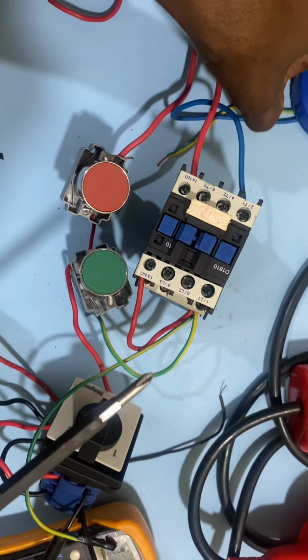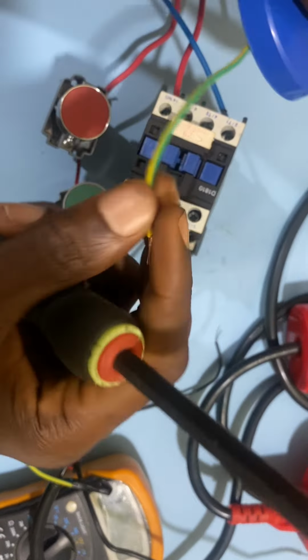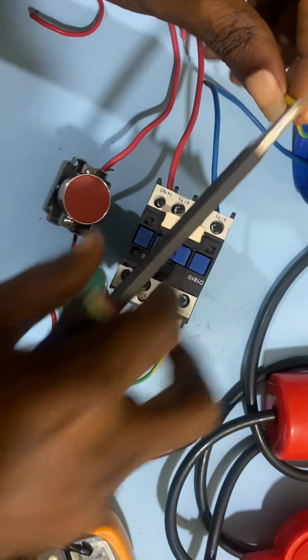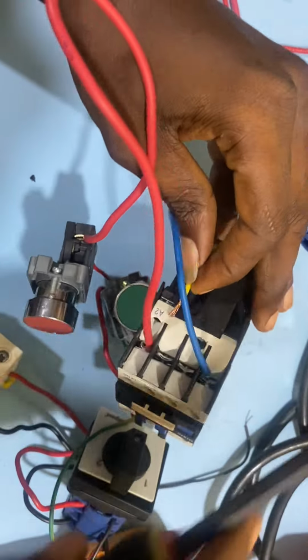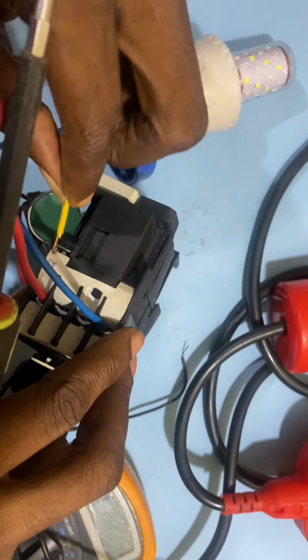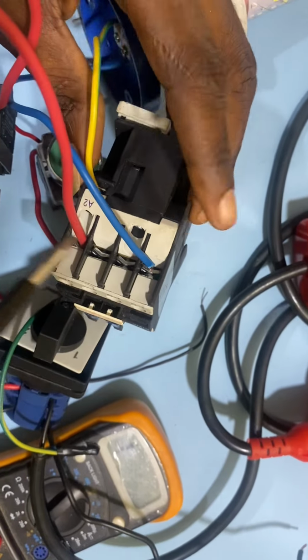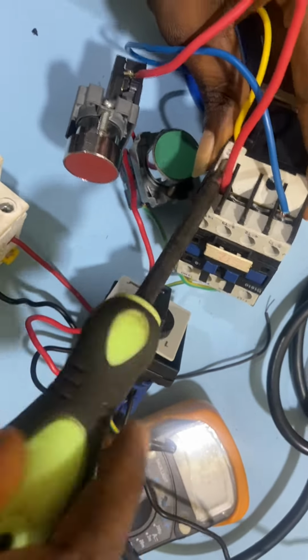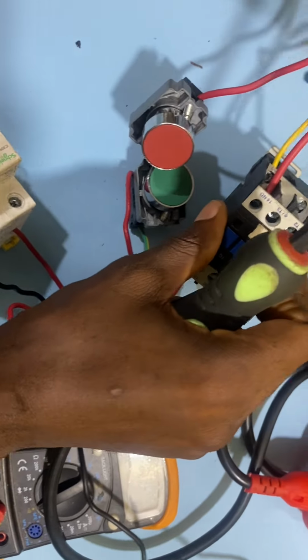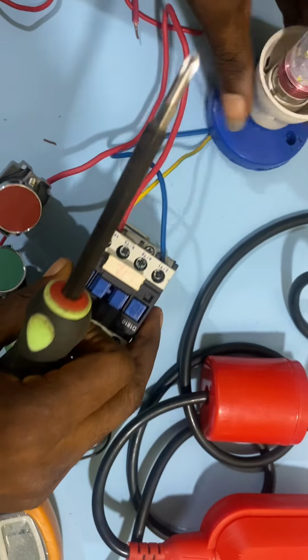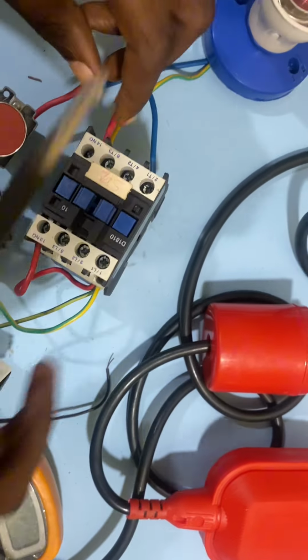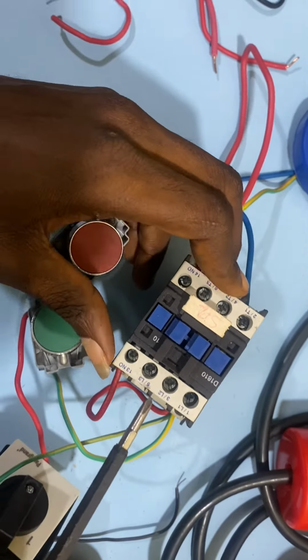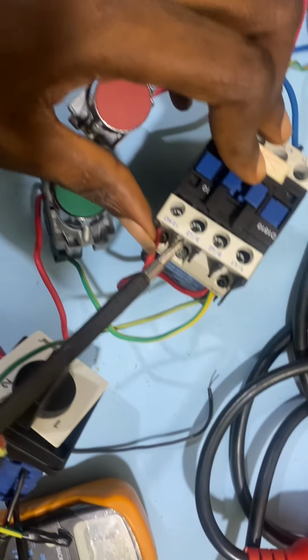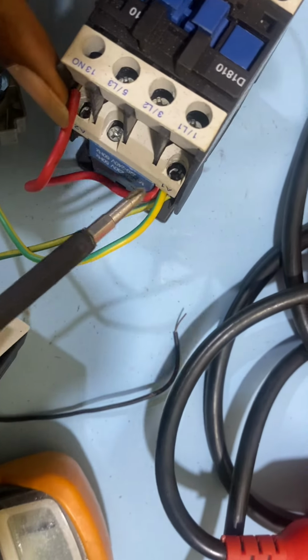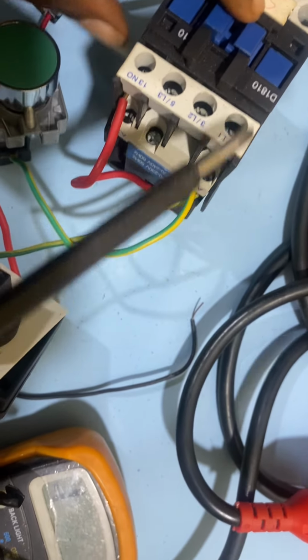So I want to connect the neutral. This is my zoomer neutral. So I'm going to connect it to the neutral contact of the contactor. I told you earlier that if you are using this side, it's still the same neutral. So I'm going to connect the neutral here. That is the neutral of the contactor. So I'm done connecting it to the neutral of the zoomer load. That is my load. So I'm done with that. So the next thing is to bring in the supply to T1 of the zoomer. You either take it from normally open contact or you take it from here. So I'm going to take from my live supply now to T1.